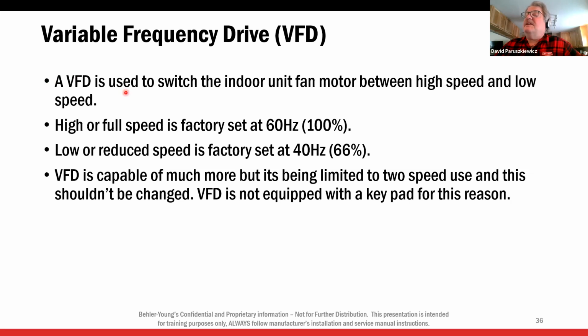So the VFD is used to switch the indoor unit fan motor between high and low speed. High speed, 60 hertz, low speed, 40 hertz. Again, the VFD can do a lot more than that. This unit is not designed for it. Don't overthink it. This is really pretty simple.